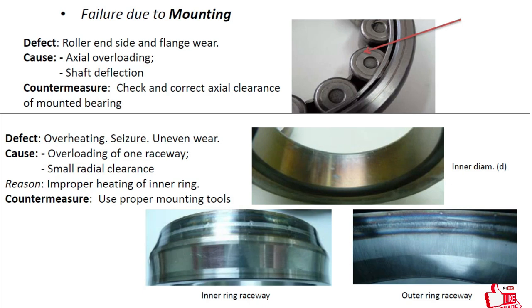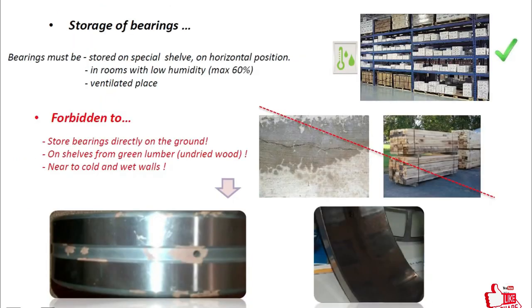The storage of bearings: bearings must be stored on a special shelf in horizontal position in rooms with low humidity, maximum 60% humidity. Above that there may be a chance of corrosion. Forbidden: storing bearings directly on the ground, on shelves from green lumber, or near cold and wet walls.